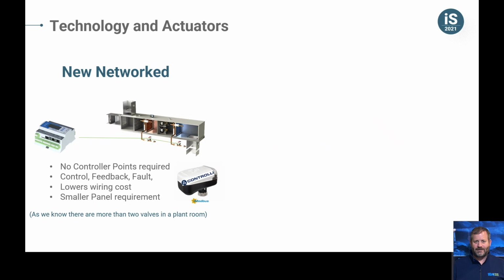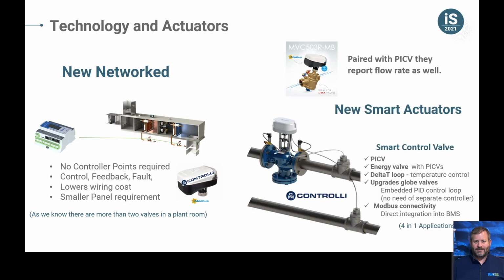And of course, there's more than 2 valves in a plant room. If you pair the same actuator with a PICV valve, you also have the capability of reporting the flow rate as well. On larger plant valves, they have a new smart actuator that can act as a PICV valve, an energy valve. It can control the temperature. You can use it to upgrade older globe valves with their installation kits. And then they're also Modbus connectivity. So there's 4-in-1 applications in one product.